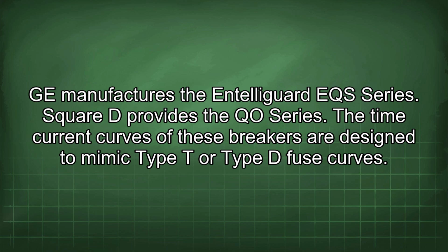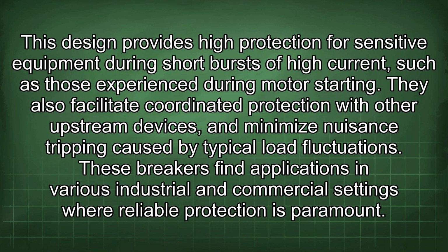The time current curves of these breakers are designed to mimic Type T or Type D fuse curves. This design provides high protection for sensitive equipment during short bursts of high current, such as those experienced during motor starting. They also facilitate coordinated protection with other upstream devices and minimize nuisance tripping caused by typical load fluctuations.